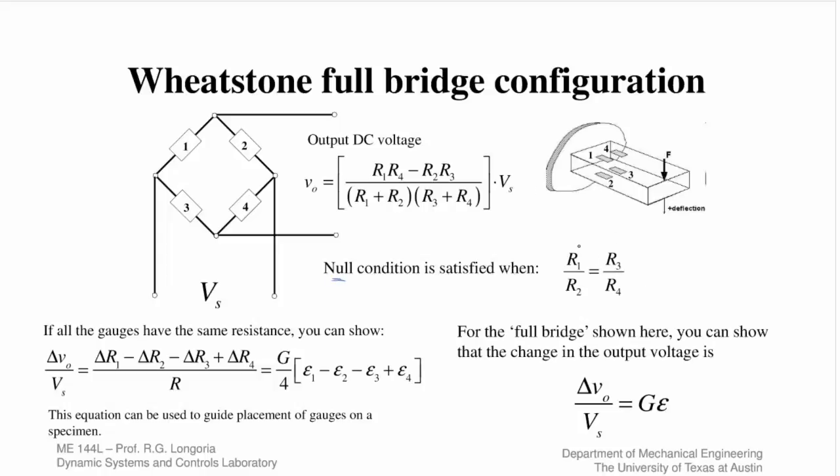You might have imbalances here, so sometimes you have circuitry that will balance the bridge and give it a null condition. That way it's zero when there's no forces applied. If the ratio of resistance one to two is equal to the ratio of R3 to R4, then this will give you a zero output. Otherwise, you need to have a balancing circuit that will make the zero value when there's no forces applied.